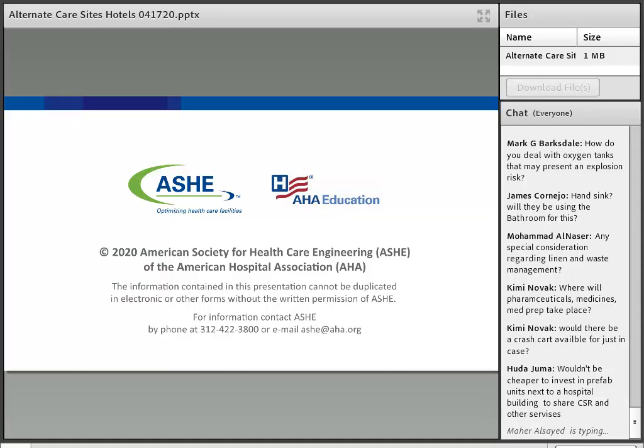One of the items that we have looked at, if we were in this hotel setting, is really to build what we would call a sally port or a vestibule on a hotel wing, and that would be our differentiating pressure location between the COVID-19 potential patients and the other locations. When we think about negative pressure, it's really a containment measure. By placing that type of sally port or vestibule there, we could maybe use only a single HEPA filter or HEPA air scrubber, and that would create that containment measure to separate those two locations.